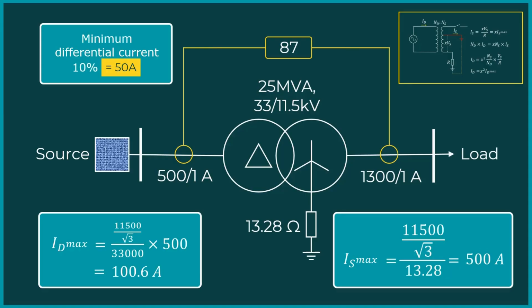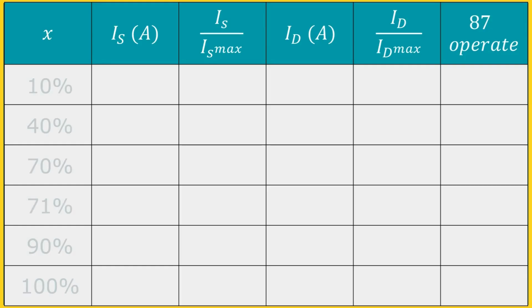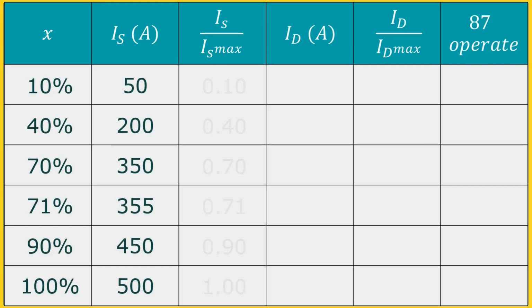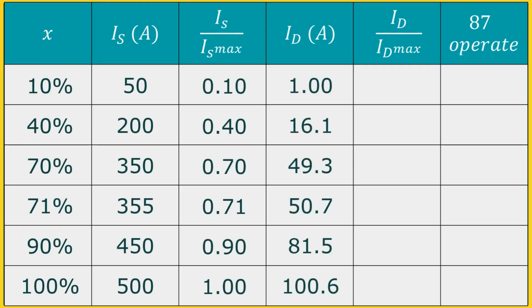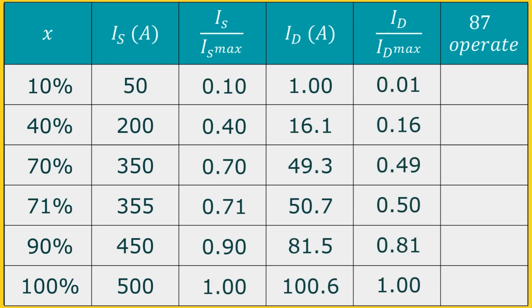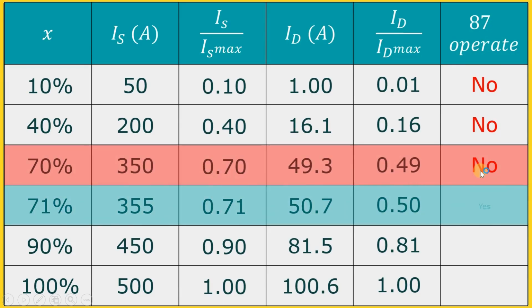For this specific example, let us see how the delta side current and star side current vary with respect to fault current position. In this table, we have calculated the star side current as well as the delta side current with respect to the location of the fault from the neutral point. We can see that up to 70% of the winding, the delta side current is less than 50 ampere, and hence the differential relay 87 will not pick up. It will pick up only after this point.